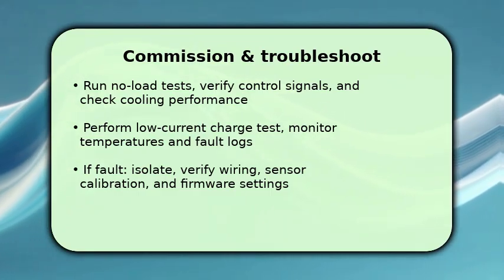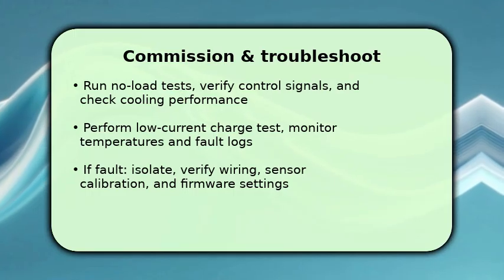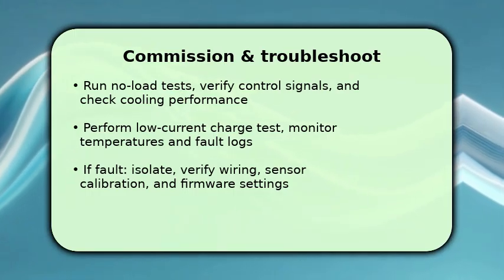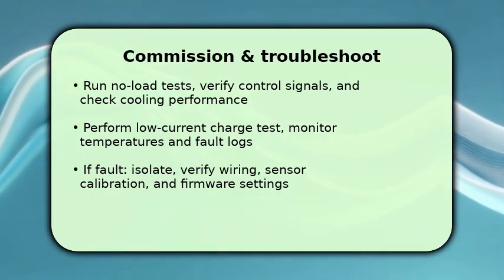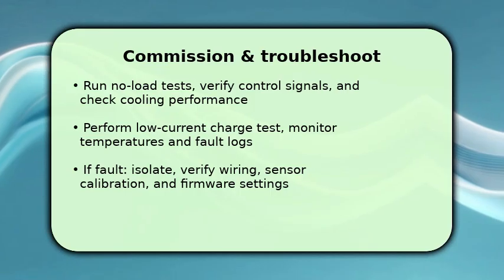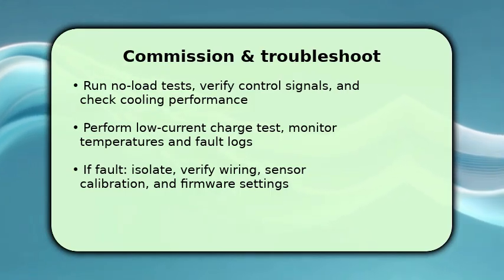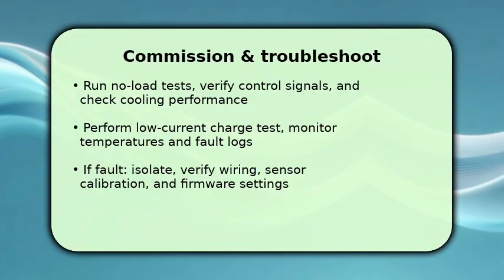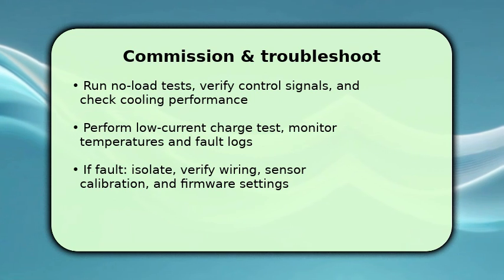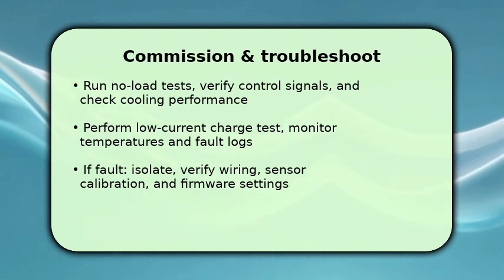Next, run a low-current charge trial with a test load or compatible vehicle while monitoring temperature, voltage regulation, and communication handshakes. If a fault appears, immediately stop and isolate the supply. Check contactor coil wiring, sensor calibration, and PLC addresses. Make sure firmware settings match the physical limits.